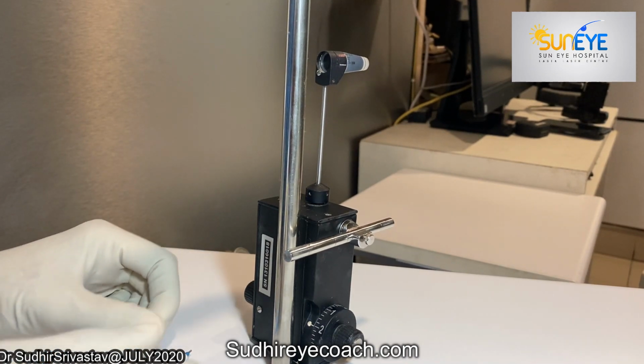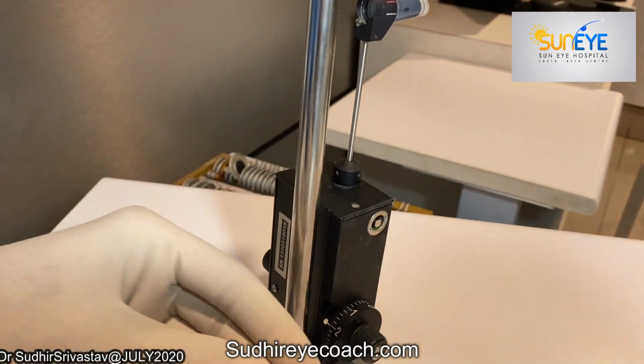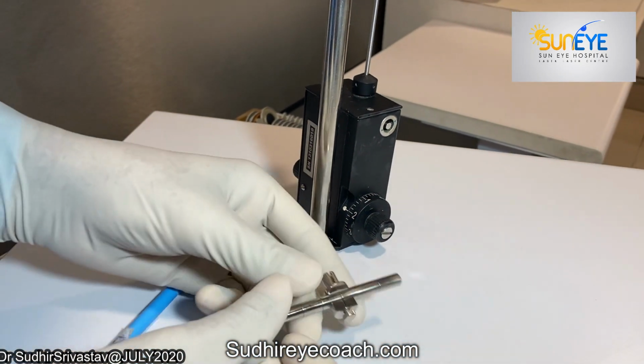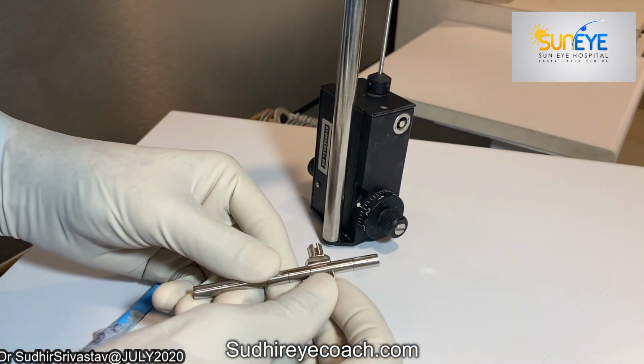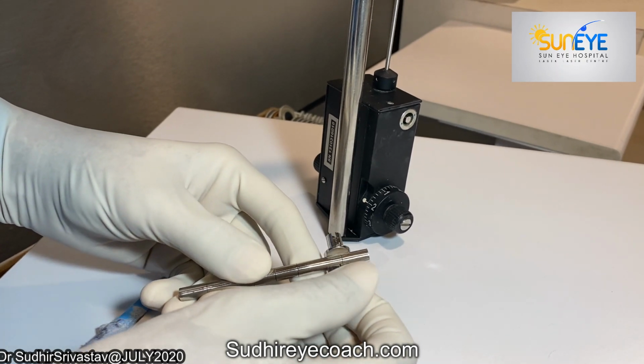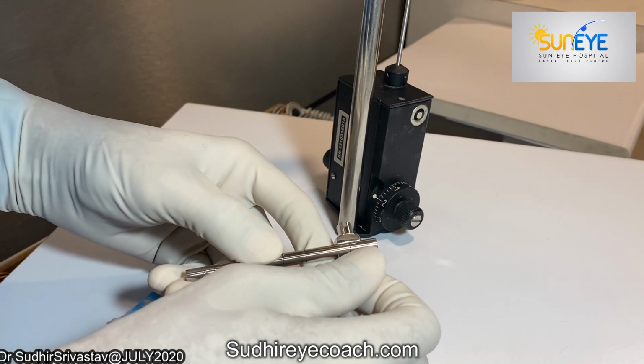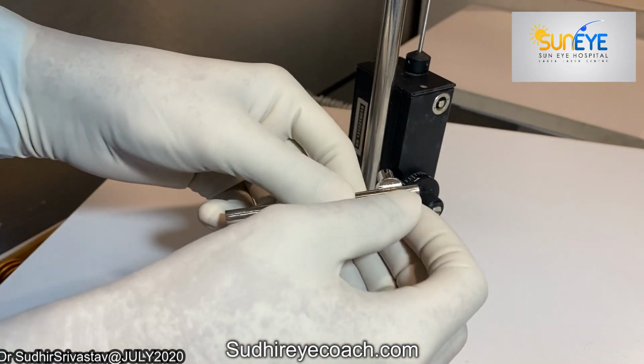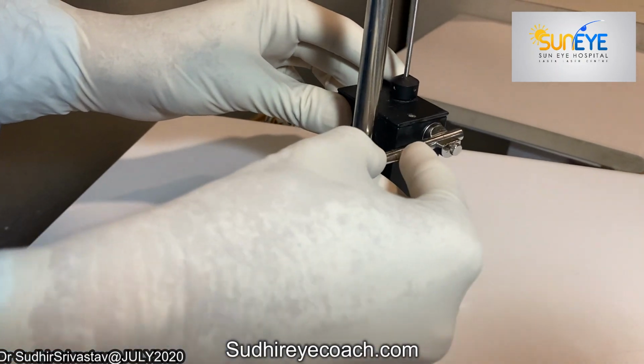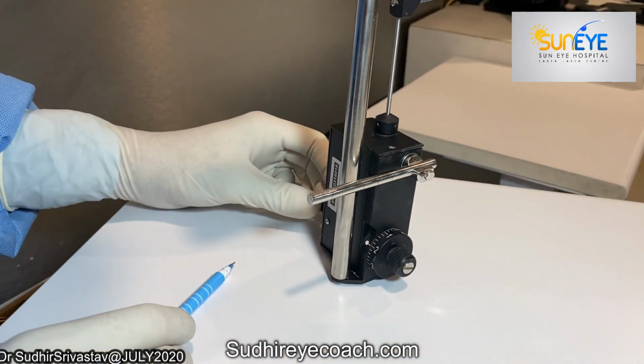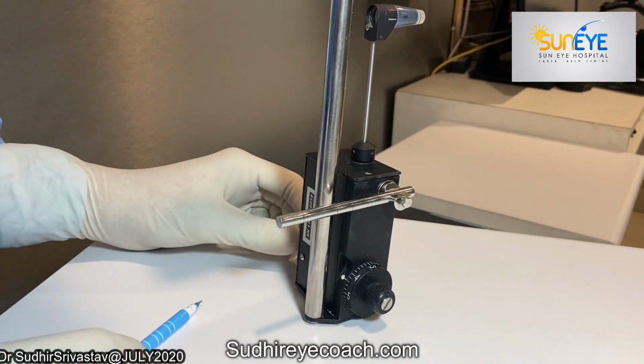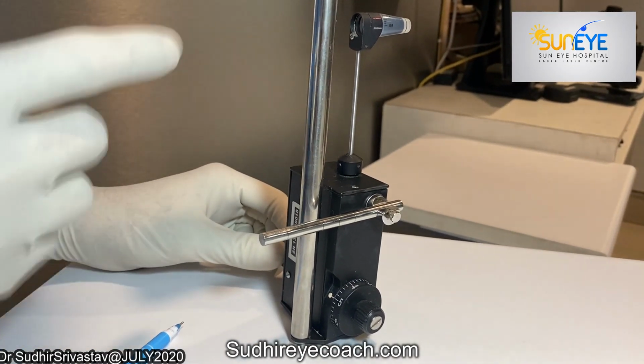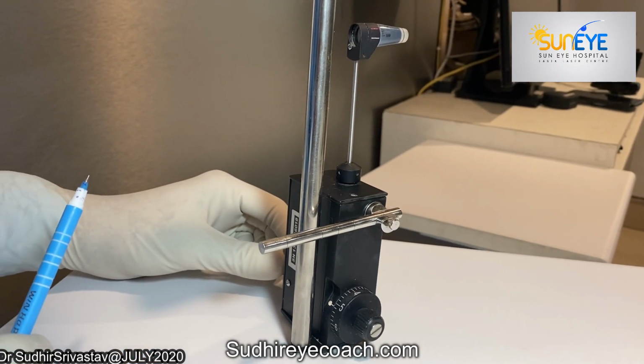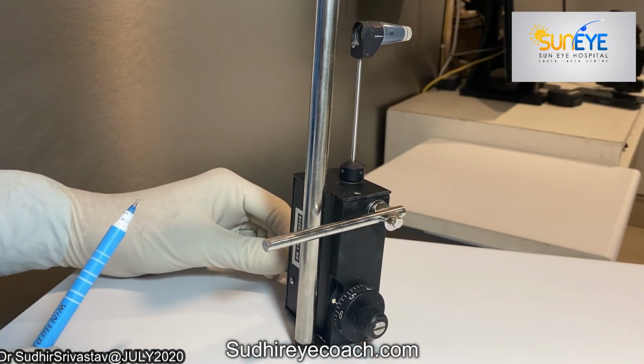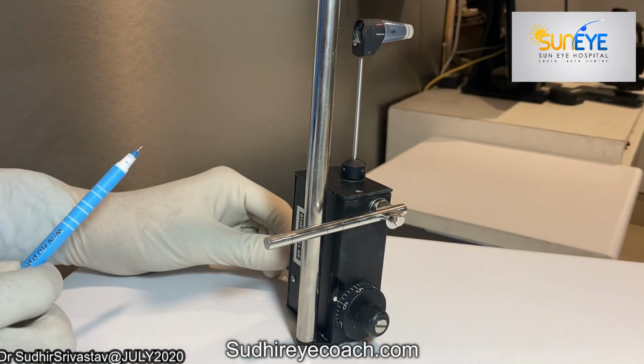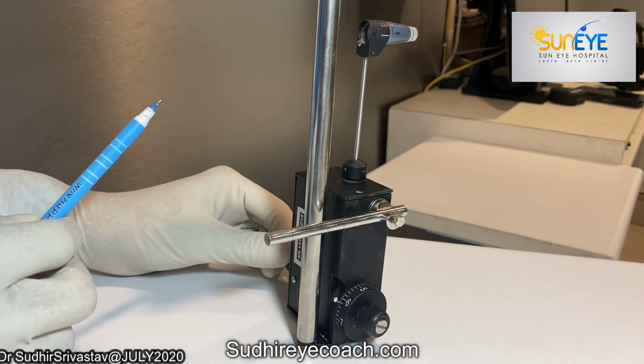Now in the next step, we will remove the device, and we will tighten this weight device at the marking 60. We apply it back, and now we will turn the knob again. Now we go from reading 5 to 6 while observing the movement of the applanating cone. Here we are moving from 5 to 6. Here we have seen the movement of the applanating cone.